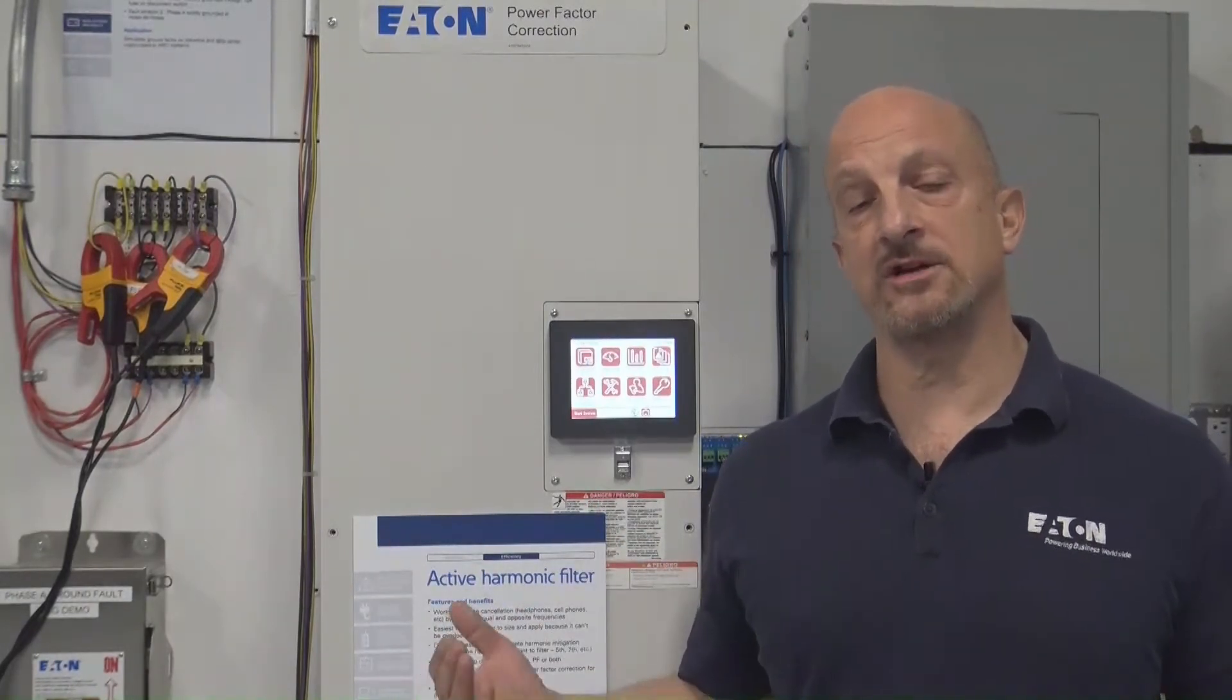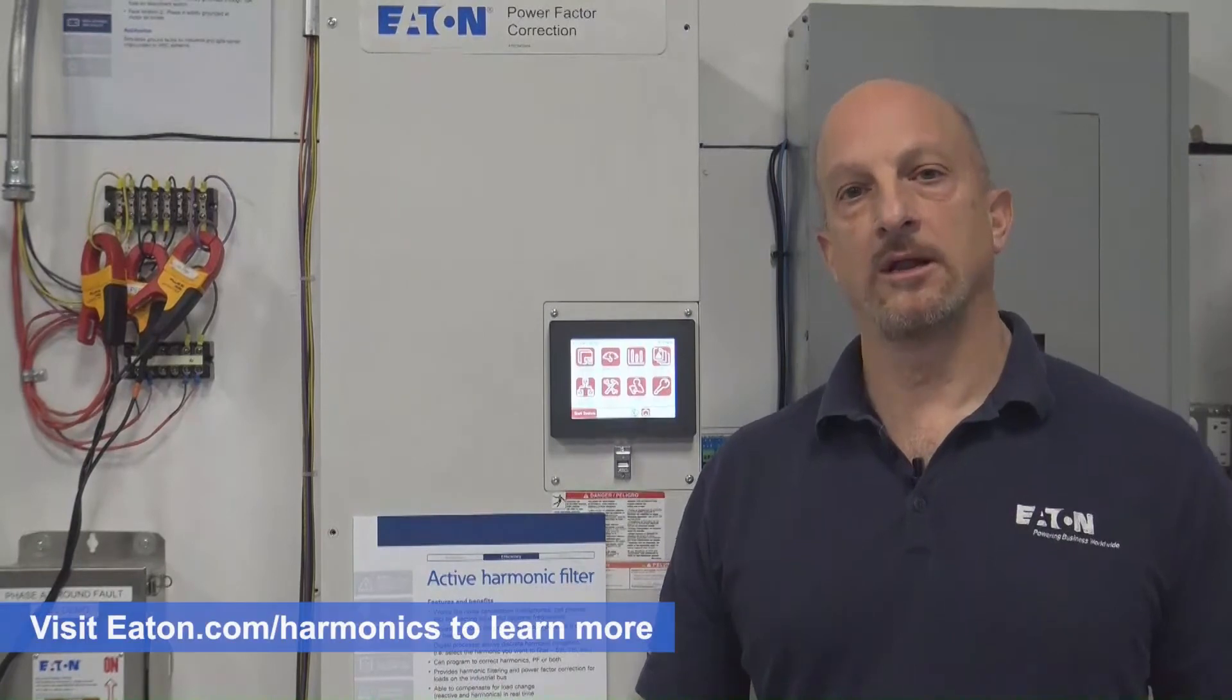They typically come in 50 or 60, 100, 200 amp, 300 amp units, and then you can parallel them. The other nice thing about these is you can't overload them because once they stop putting out the amount of harmonic current that they can put out or the power factor correction they put out, they stop producing at that level, whether it's 100 amps or 120 amps or whatever the case may be.